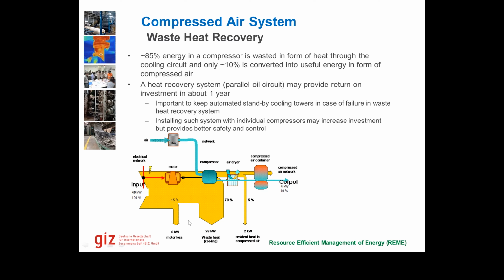So in colder areas, we have a typical return on investment of about 1 year. In hot areas or warm areas, the payback might be around 2 years. We need to have standby cooling towers with this as well, obviously, but these will only be standby. The main cooling needs to be done by the heat recovery system. This recovered heat can be used to heat up water as well as heat up air.